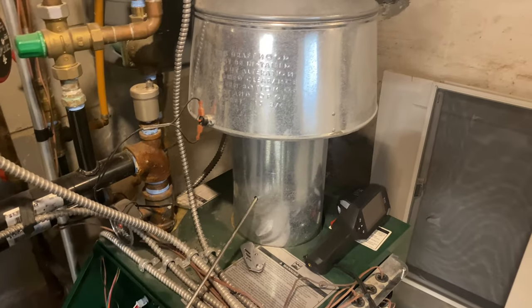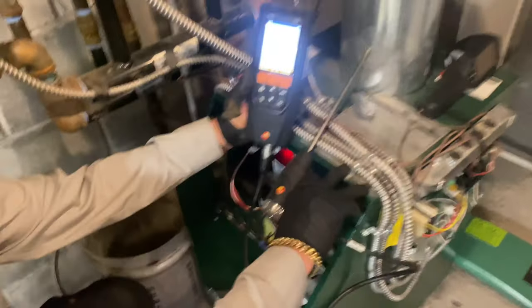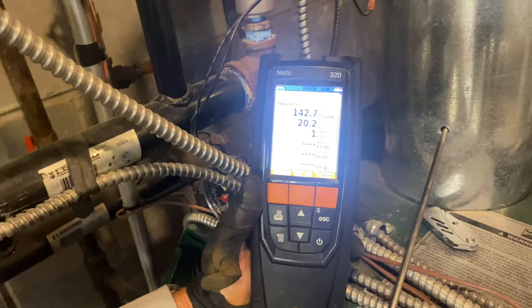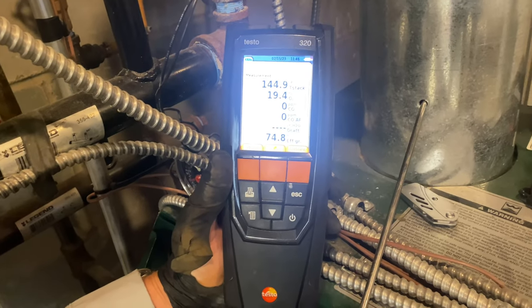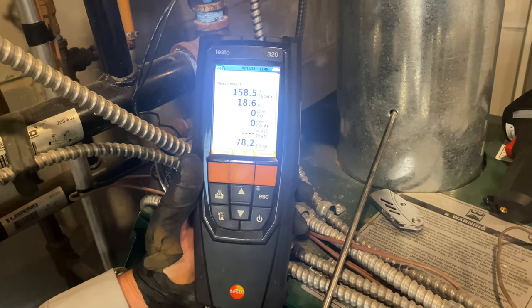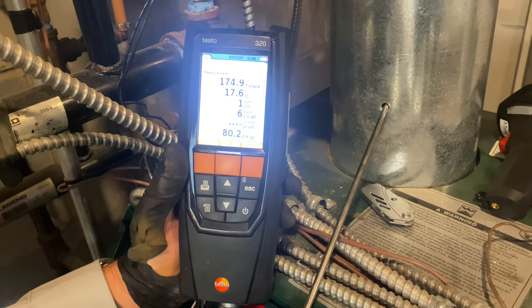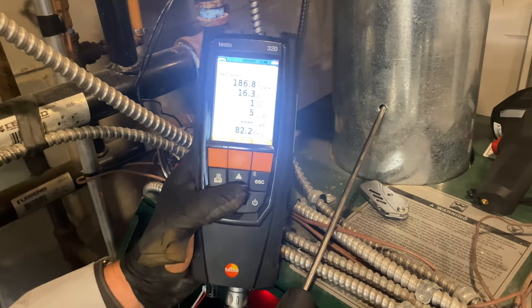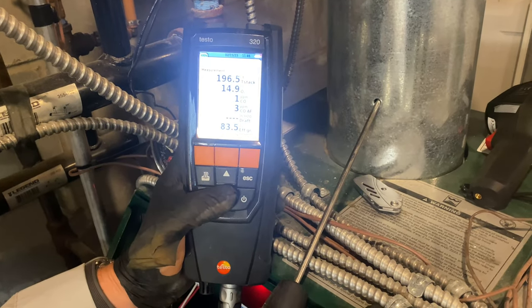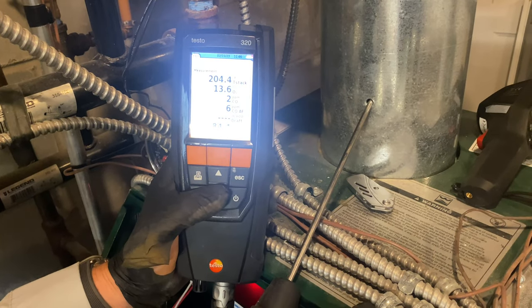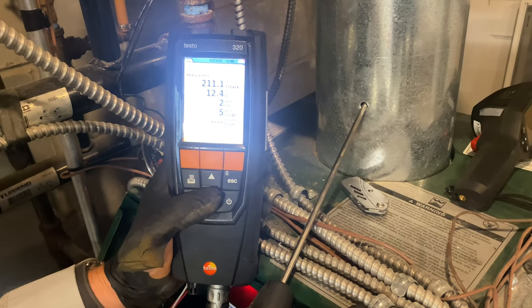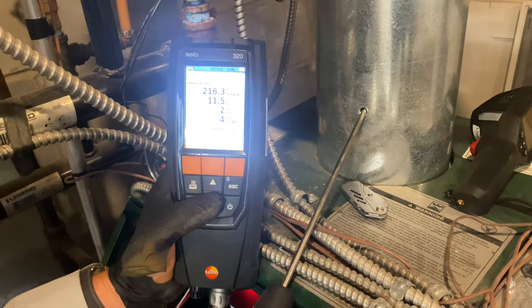Halfway, right there, okay? We're going to take a look at these numbers, we're going to see them climb up, obviously this temperature of the stack. We're going to see O2 drop. We're going to see parts per million of carbon monoxide. We're also going to see gross efficiency, EFF gross, GR—that's the efficiency of the boiler. For every dollar of gas it's using, 85.1 cents and climbing is actually dedicated to heat the house.